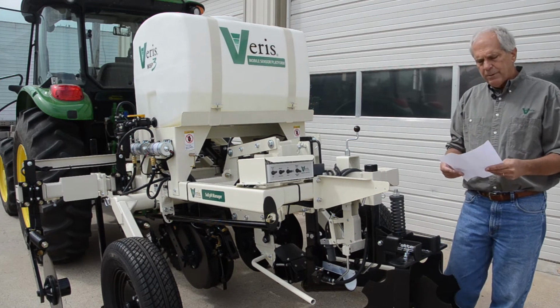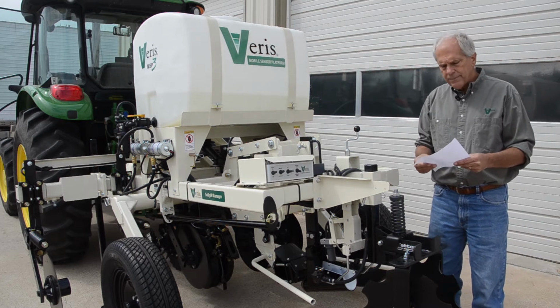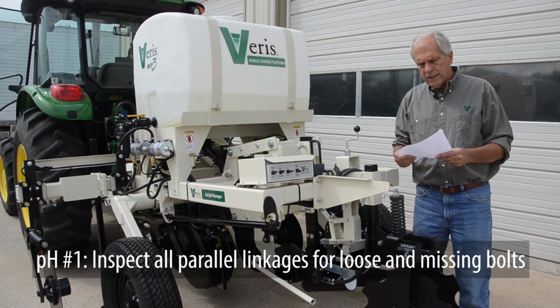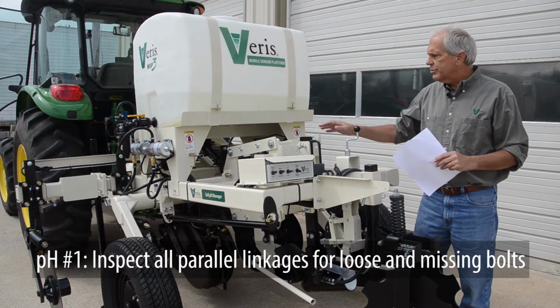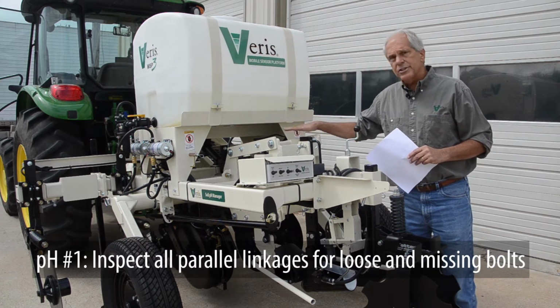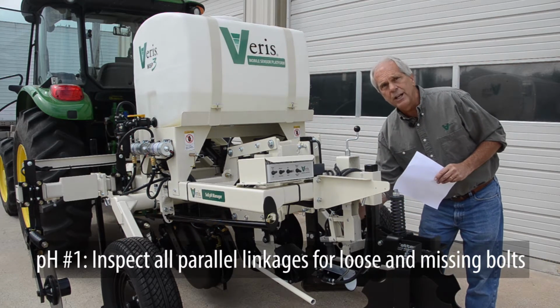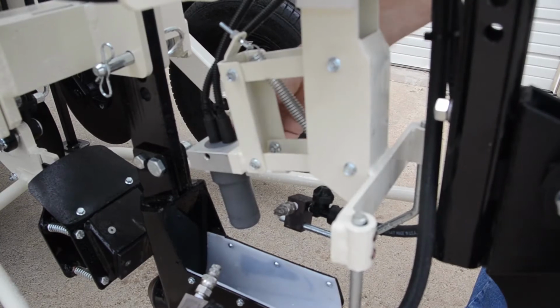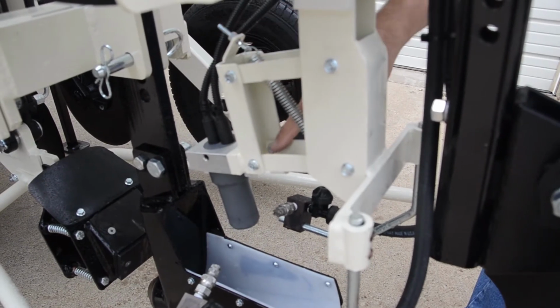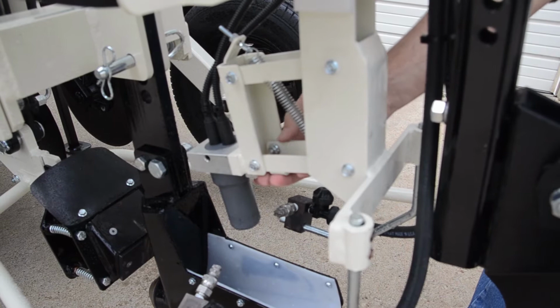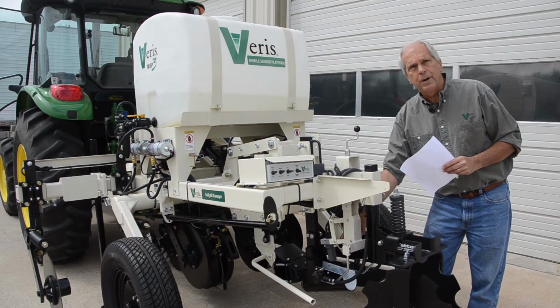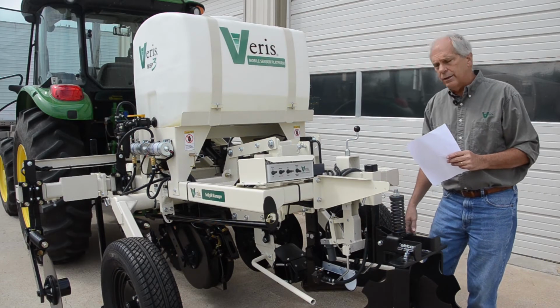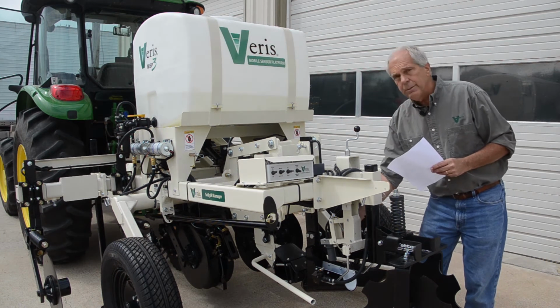The first item on the pH checklist is to inspect all parallel linkages for loose or missing bolts. The parallel linkages are the sampler shoe and the electrode holder. We want to look and make sure all these bolts are in place. If any bolt's going to work loose on a machine, it's bolts on a parallel linkage — those are the ones most likely to work loose. So let's make sure they're all in place.